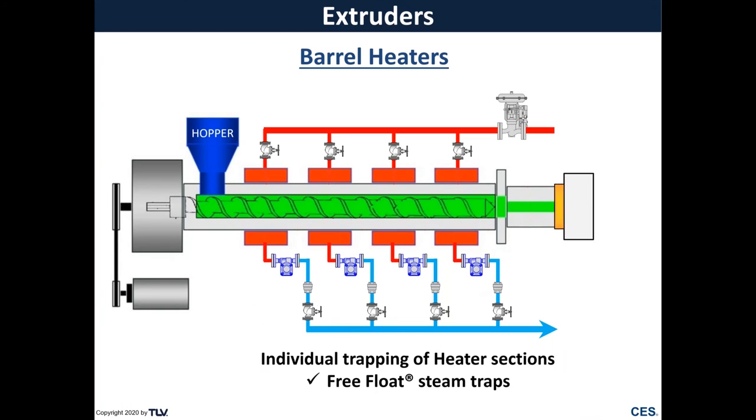So individual trapping of each barrel heater using free float traps is the most effective way to ensure complete continuous drainage of condensate from the heaters and maintenance of product temperature.